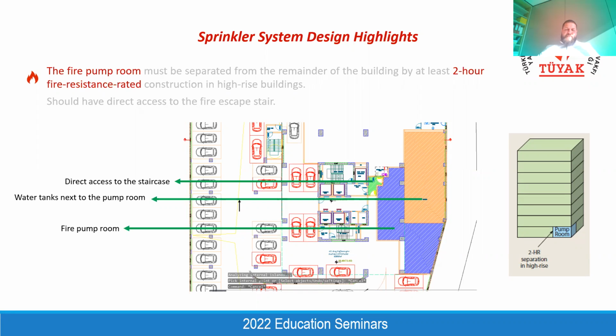The fire pump room shall be a 2-hour fire rated separate zone. That's why we need to design its perimeter walls accordingly. They should be at least 20 centimeter block walls to fulfill this fire rating requirement. And also the most important thing, the fire pump room shall be just next to the fire tanks. If we have separate fire water tanks, reservoir, and fire pump room, it's really difficult to get this water to the fire pump room. Some of the architects require this due to the lack of area within the building, but it's not a correct design. We always keep the water tanks just next to the fire pump room so that we have these pumps in connection with the water, and we can keep the system convenient all the time.